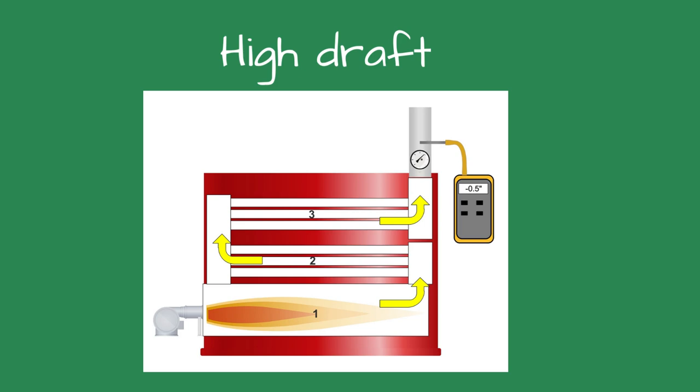Rubbing my chin, I looked at the boiler, piping, and flue. After inserting the probe from my combustion analyzer into the flue pipe, I saw the stack temperature was high, about 100 degrees higher than normal.